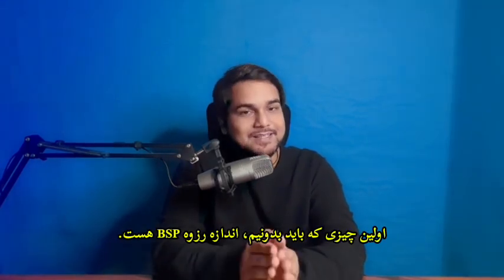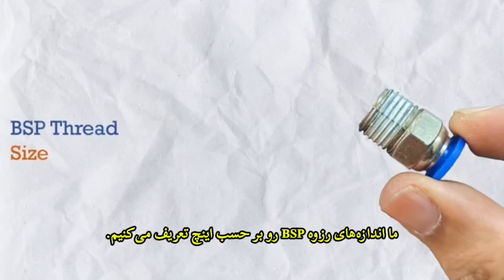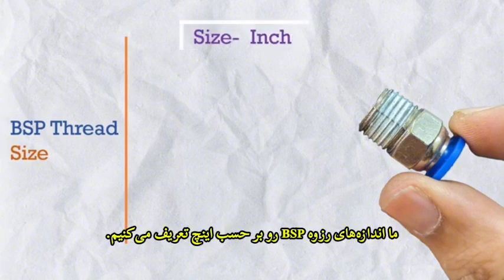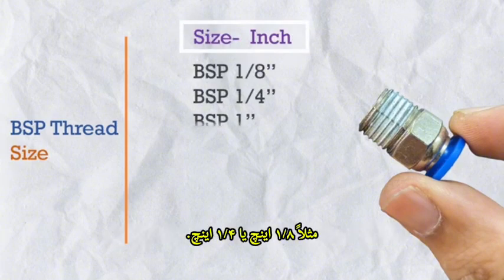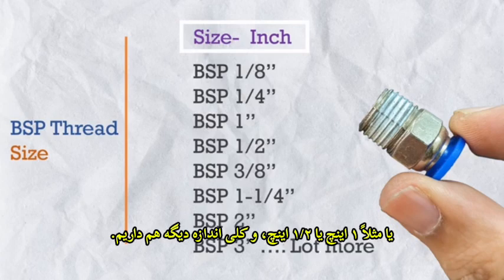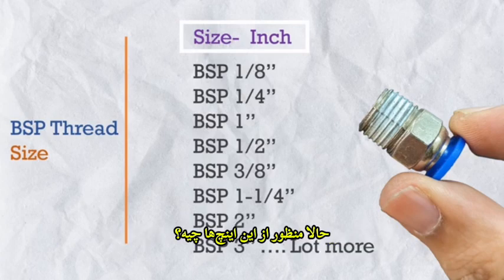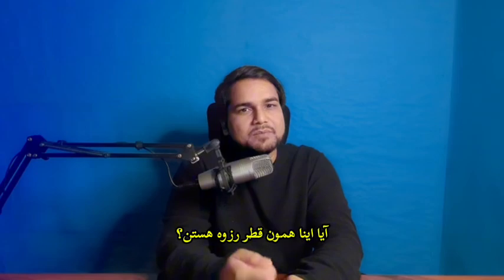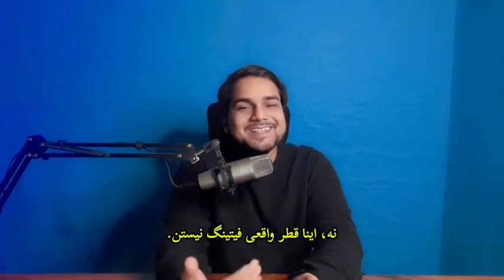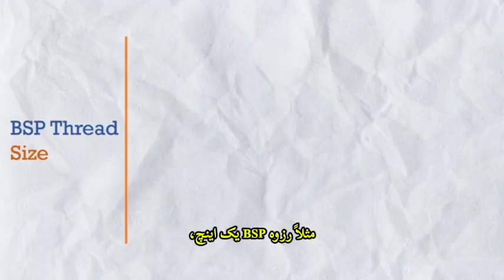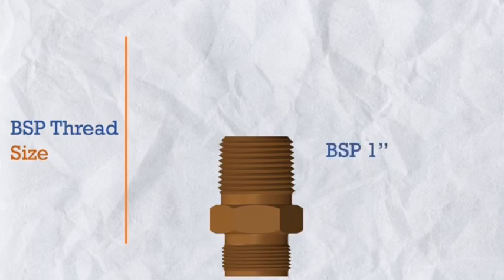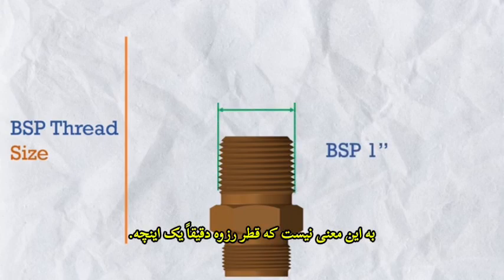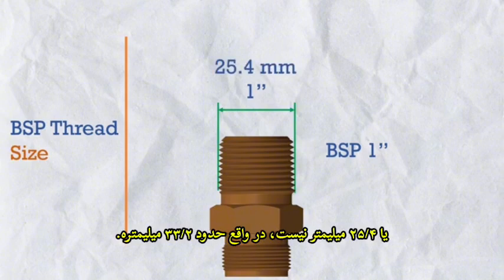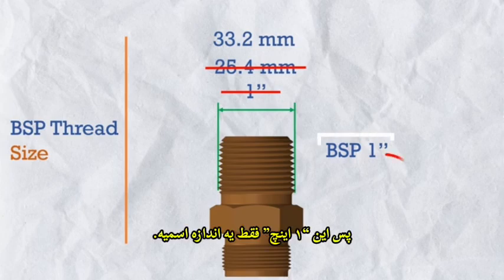So the first thing is the size of BSP thread. We define the BSP thread sizes in inches like 1/8 inch, 1/4 inch, 1 inch or 1/2 inch, and there is a lot more. So what does the inch mean? Is this the diameter of the thread? No, this is not the diameter of the thread. For example, 1 inch BSP thread doesn't mean that the thread diameter is 1 inch or 25.4 mm. It's actually 33.2 mm.